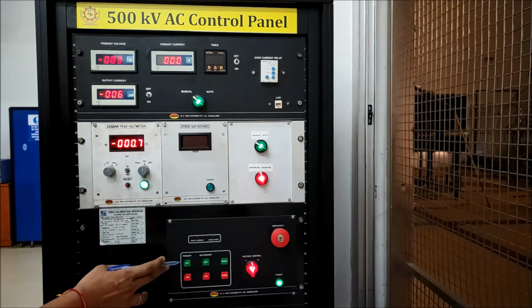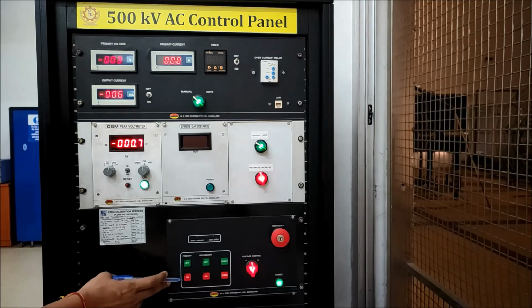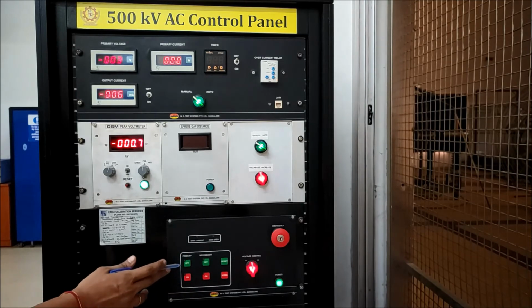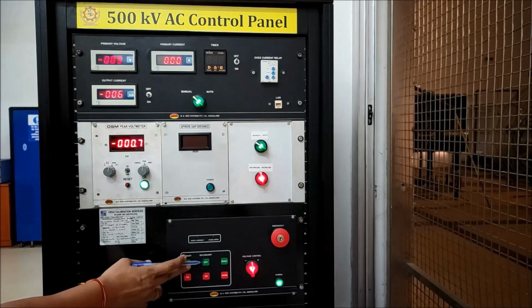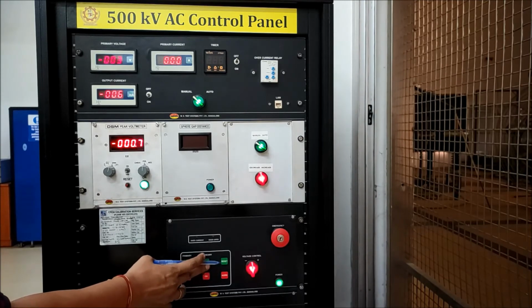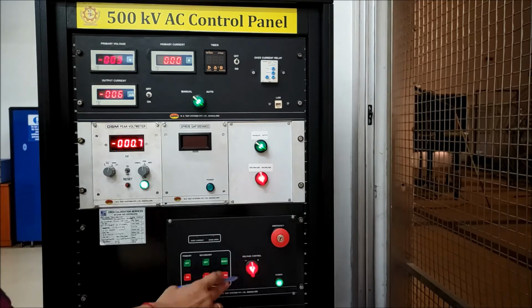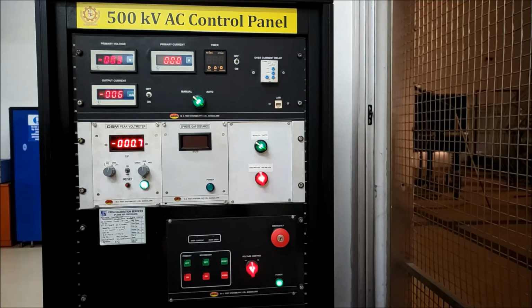Okay, then this is the control unit. This is the primary side and this is the secondary side. This is primary off, primary on, secondary off, secondary on. This is the reset button and this is the horn. And this is the voltage regulator switch. With the help of this switch you can increase or decrease the voltage. And this is the emergency button. If any short circuit appears in the test hall or control room, you can press the switch and the voltage suddenly falls to zero.